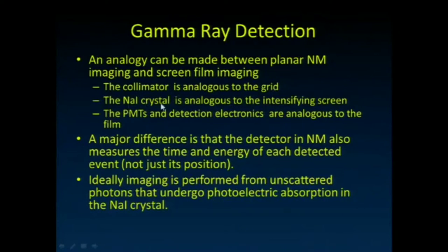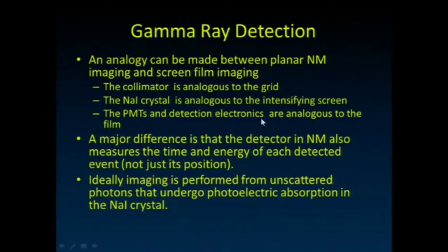The sodium iodide crystal we use in planar nuclear imaging is analogous to the intensifying screen or the input phosphor in CR-type imaging. The photomultiplier tubes and detection electronics are analogous to the film or digital detectors in digital radiography. The major difference is that the detector in nuclear medicine also measures the time and energy of each event, not just where it happened on the imaging detector.